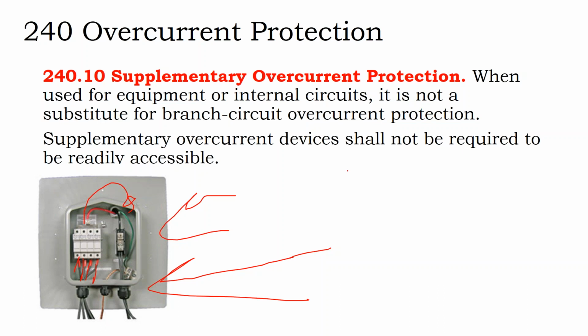But you need to have additional fuses there so that if this ground faults, and maybe another circuit is ground faulting as well, you don't want your 3 circuits of power to outflow through that ground faulting single conductor, because now you have 3 times the amperage flowing through the wire. And so you might put additional fuses into your circuits to provide additional layers of protection. These kinds of fuses are not a substitute for your main overcurrent protection device.